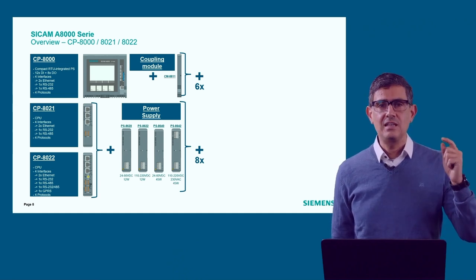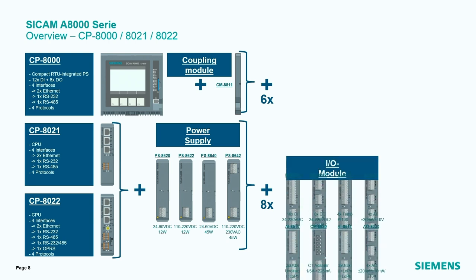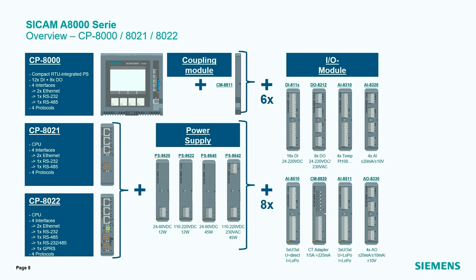For expansion you need the CM8811 coupling module. For the other RTUs — the CP8021 and CP8022 — you can attach additional modules without the need of a coupling module. The available modules include binary input modules with 16 inputs each, and binary output modules such as the DO-8212 with eight binary outputs.